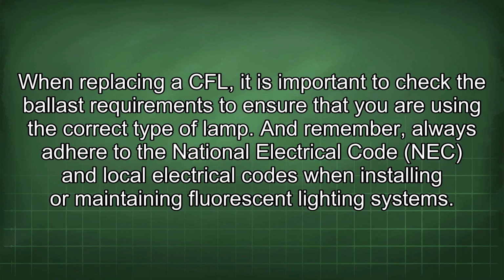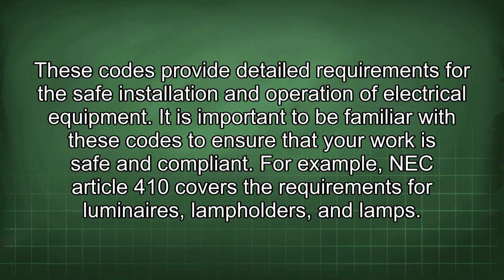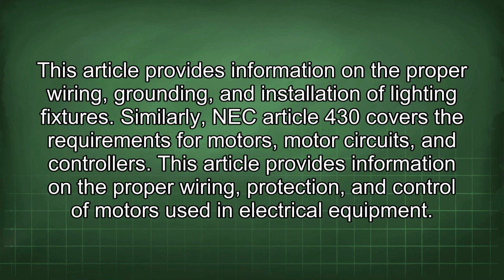When replacing a CFL, it is important to check the ballast requirements to ensure that you are using the correct type of lamp. And remember, always adhere to the National Electrical Code (NEC) and local electrical codes when installing or maintaining fluorescent lighting systems. These codes provide detailed requirements for the safe installation and operation of electrical equipment. It is important to be familiar with these codes to ensure that your work is safe and compliant. For example, NEC Article 410 covers the requirements for luminaires, lamp holders, and lamps. This article provides information on the proper wiring, grounding, and installation of lighting fixtures.